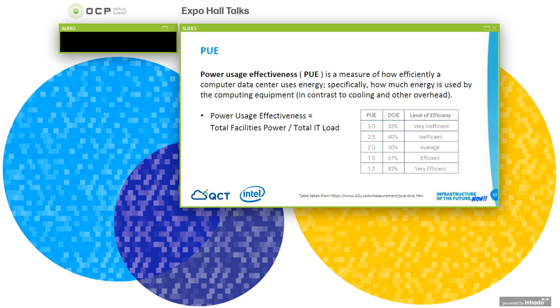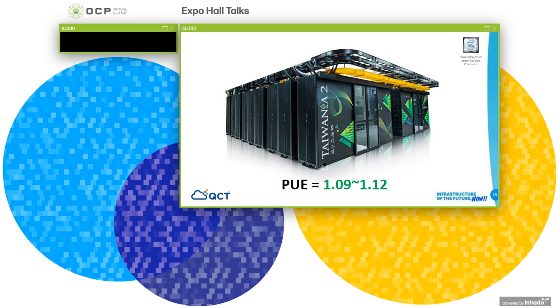PUE stands for Power Usage Effectiveness, and DCIE, Data Center Infrastructure Efficiency, are the two indexes used to measure how efficiently a computer or data center uses energy, with DCIE being the inverse of PUE. A PUE value below 1.2 means very efficient power usage. Taiwania 2 scores a PUE rating between 1.09 and 1.12, classified as a very efficient supercomputer system.